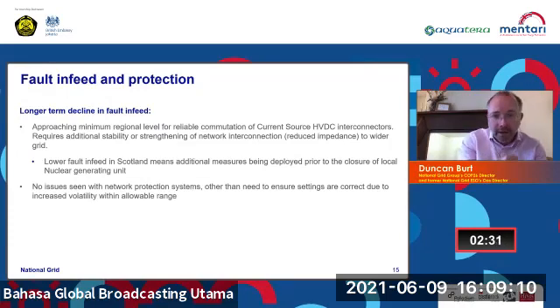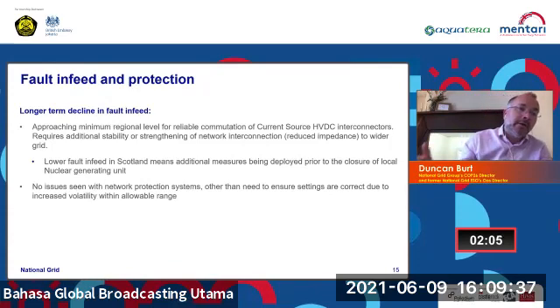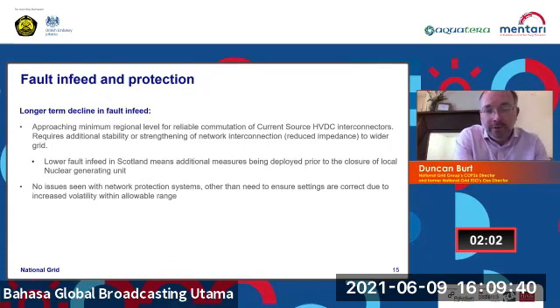They need a local strong AC signal to connect to, to allow them to regenerate the 50 hertz wave signal. As we see fault infeed lowering, particularly in Scotland with the closure of nuclear plant, we see a drop in fault infeed that in the future may be below what we need to reliably operate the HVDCs at maximum level. So in those areas, we're implementing additional rotational plant, synchronous condensers, and other measures to create enough stabilizing fault infeed to continue operating the network reliably and securely.